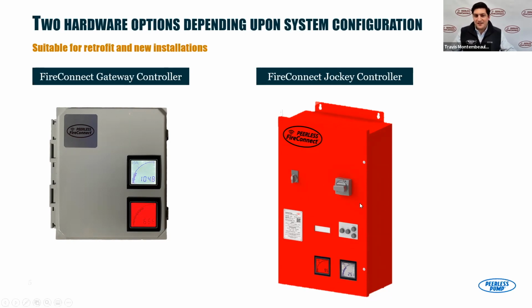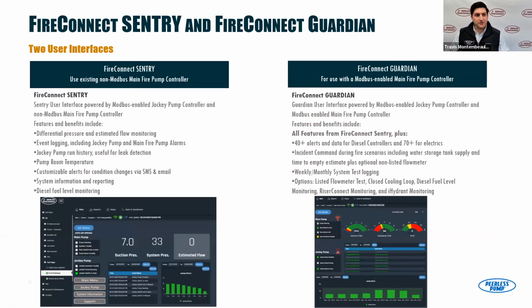But then we're capturing that data and sending it up to the cloud, just like we normally would with this gateway controller. And then we still take all those analog and digital inputs. So that suction transducer, or the pump room temperature, or the flow meter, the water storage tank. We take all those inputs and we still connect it to the IoT board that's in this jockey controller and send all that up to the cloud as well. And this is important because we now have, in an integrated package, a kind of basic version of a smart fire pump system. And so we'll go one slide further here, because this enables two different user interfaces for us.